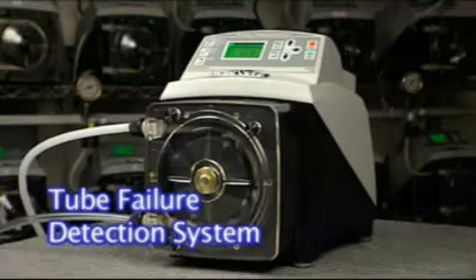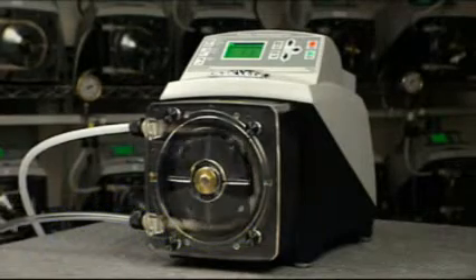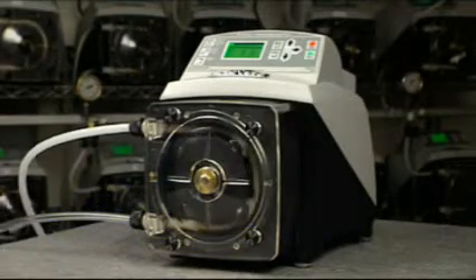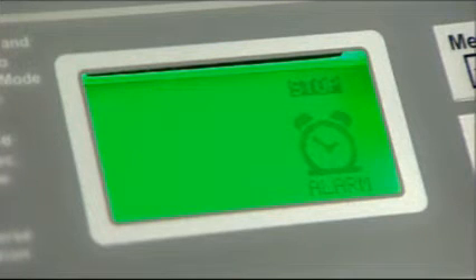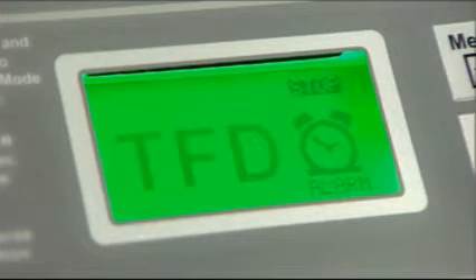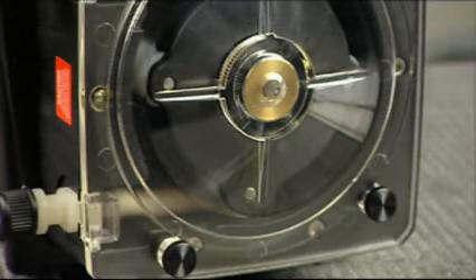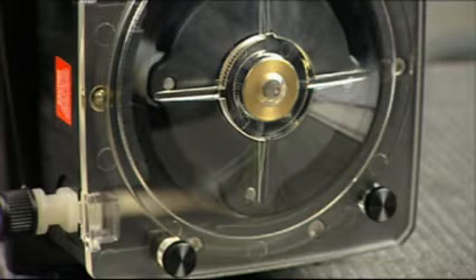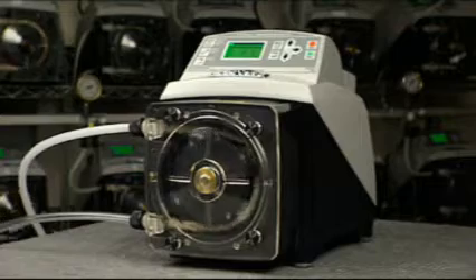The A3 features a patented tube failure detection system that will automatically shut down the pump in the event the pump tube ruptures and chemical is detected in the pump head. The system is designed to react to most chemicals, but disregard water. This exclusive feature will prevent false triggering due to rain, condensation, and washdown maintenance procedures.